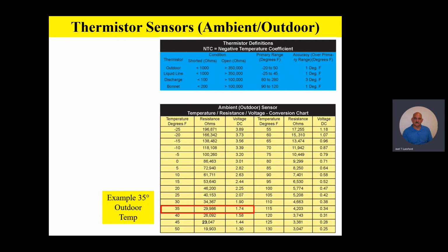An example would be, though, if your meter said OL, that means the sensor is open electrically. It's open electrically if it says OL. If it had 0 ohms, or if it had 15 ohms or some very, very low ohm number, that means that the sensor is shorted internally. Normally sensors, when they fail, they just open. They just say OL on them, and they have no reading at all. But occasionally you'll find one that's shorted inside with a very, very low ohm rating.